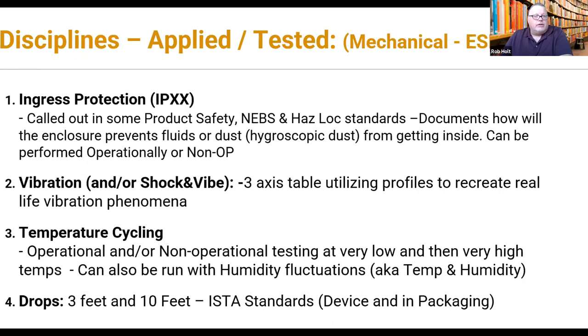Other things to consider in product safety include ingress protection — some safety standards call out a certain level, rating the unit's ability to withstand ingress of dust, hygroscopic dust, or water, such as saltwater near the ocean. Then there are validation-type tests, some of which are required for NEBS: shock and VIBE, temperature cycling, temperature and humidity cycling, drops on the device and packaging. These are important for both internal validation and possibly market-driven standards, and can help you draft your warranty plan.